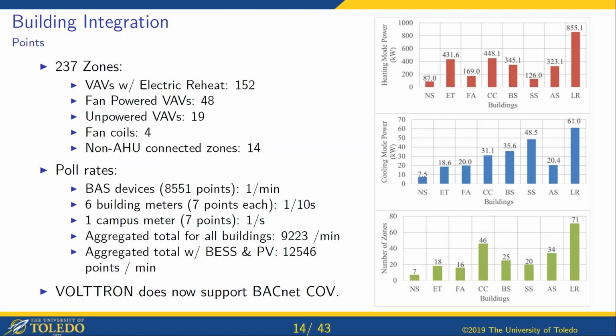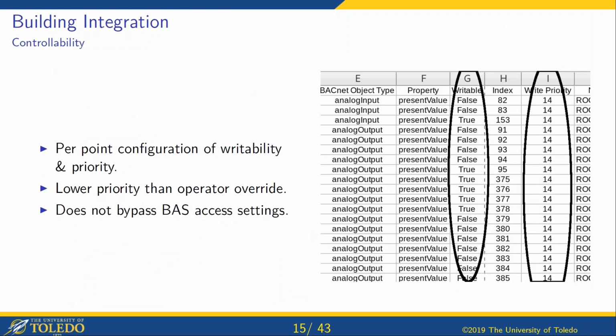So altogether, we are actually pulling about 12,500 points per minute into VOLTTRON, and storing those to analyze things later or to do things in real time. We could actually improve our pull rate if we were installing this now. VOLTTRON does now support the change of value functionality that's available in BACnet. And hopefully, I need to talk to Siemens as to whether or not this is compatible with their stuff, but hopefully we'll be able to move over to that in the near future.